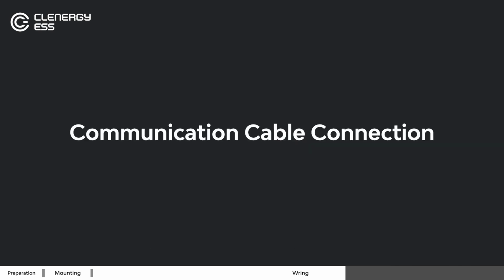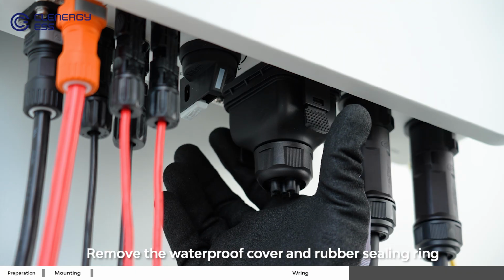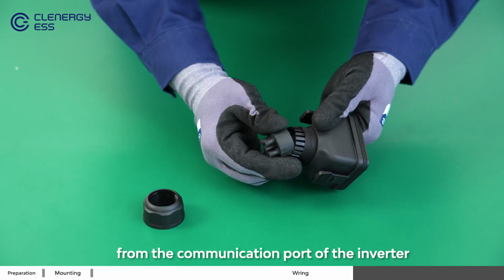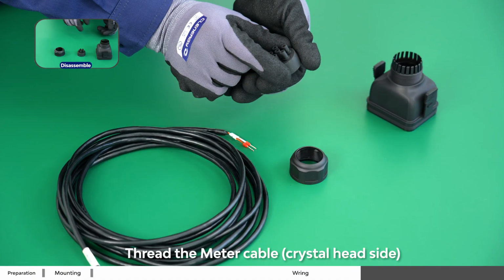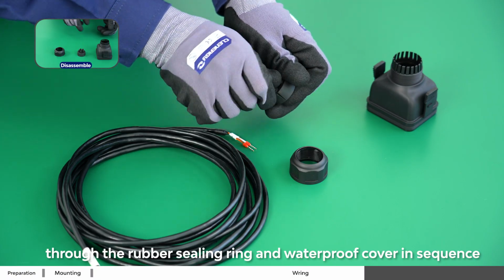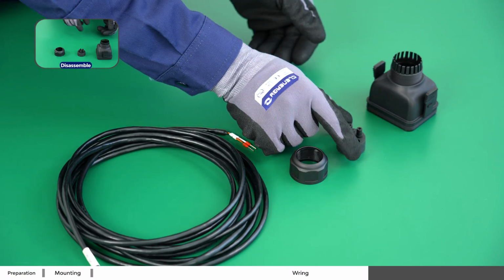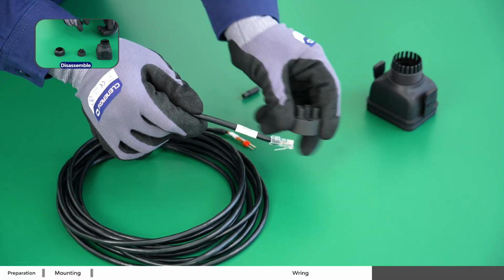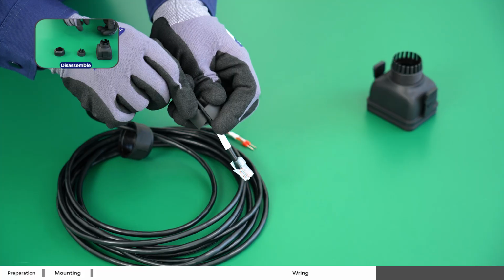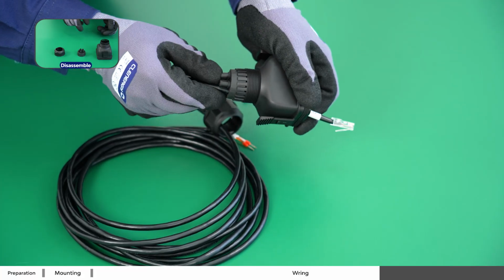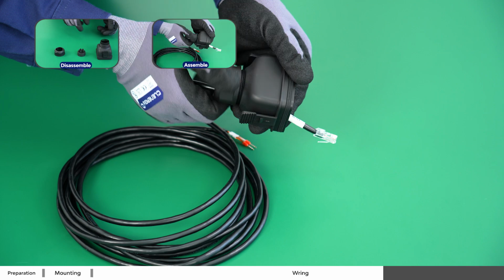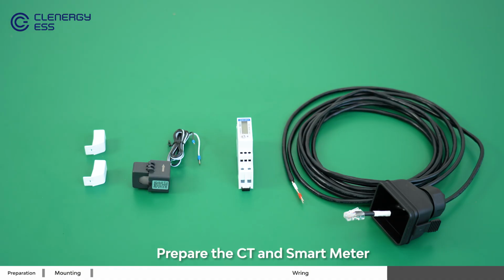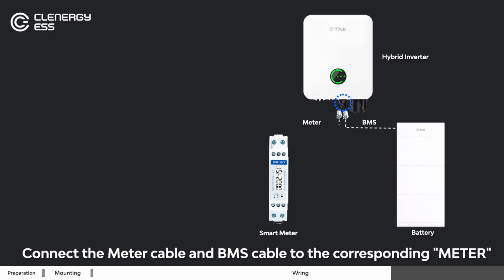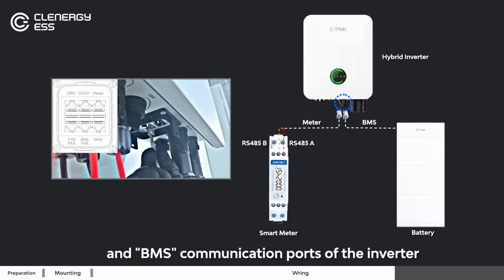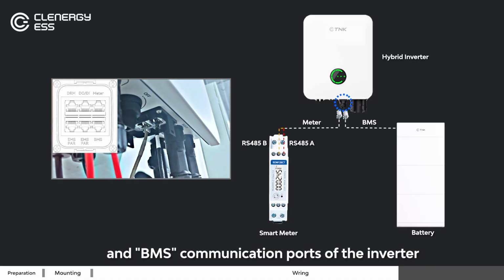polarity. Communication cable connection. Remove the waterproof cover and rubber sealing ring from the communication port of the inverter. Thread the meter cable through the rubber sealing ring and waterproof cover in sequence. Prepare the CT and smart meter. Connect the meter cable and BMS cable to the corresponding meter and BMS communication ports of the inverter and tighten the bottom.